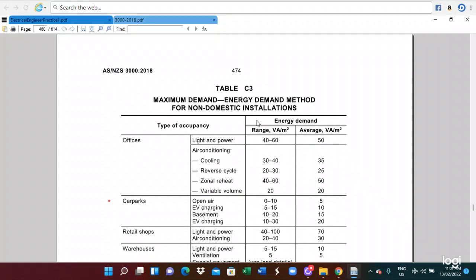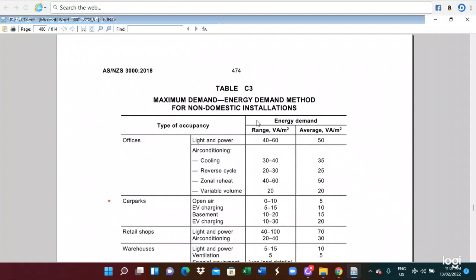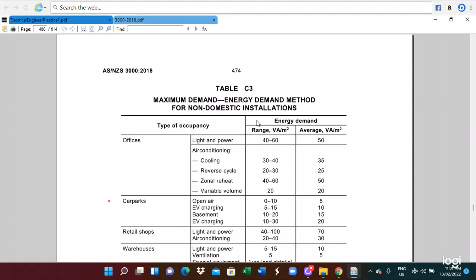The next table, C3, is a maximum demand method for non-domestic installation. This is based on the energy demand method. For every 1 square metre, how many volt-amperes are allowed depends on the office or car park, and you can calculate the maximum demand.